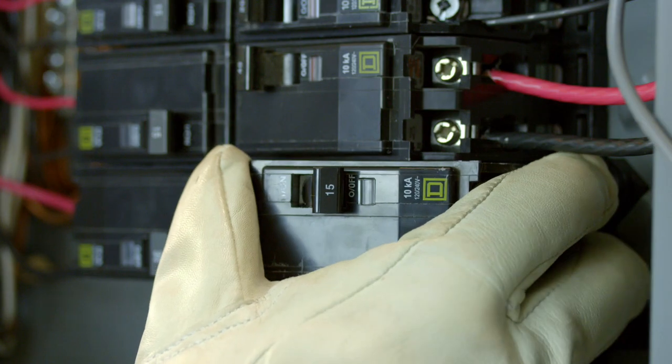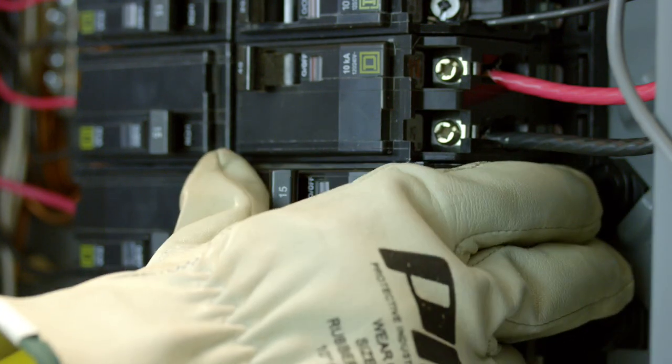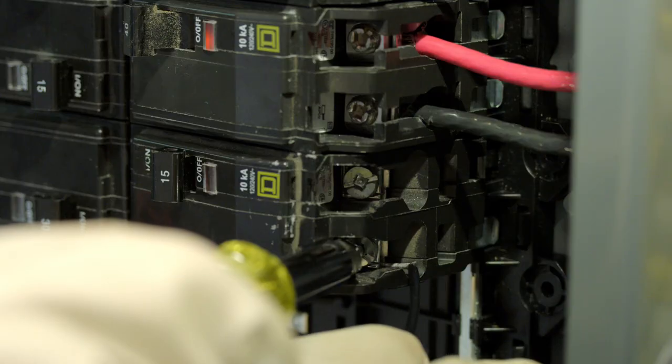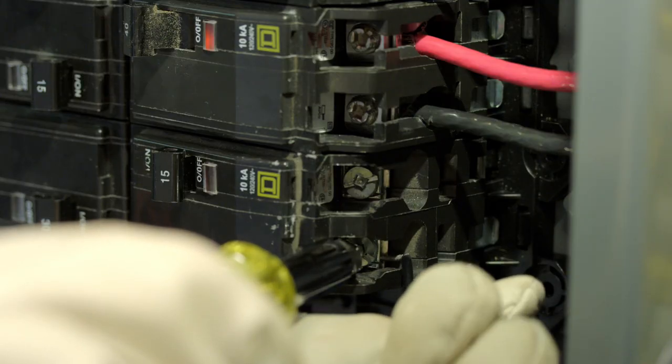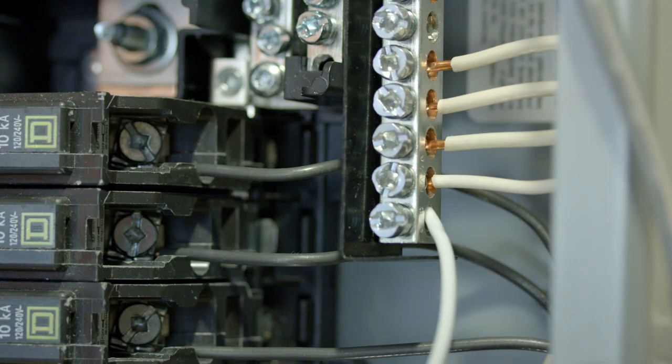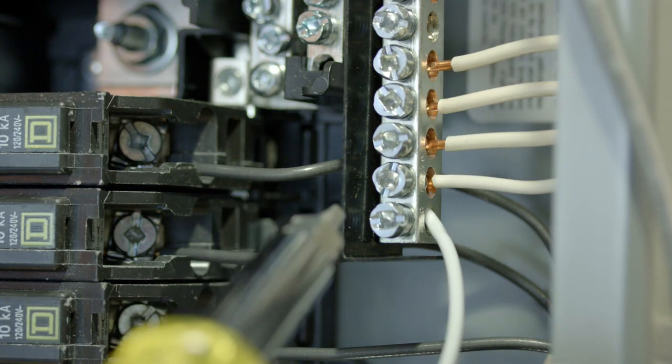Simply install the two-pole breaker into an empty slot in the panel, then connect the black and red wires to the breaker lugs. The white wire connects to the neutral bus bar.